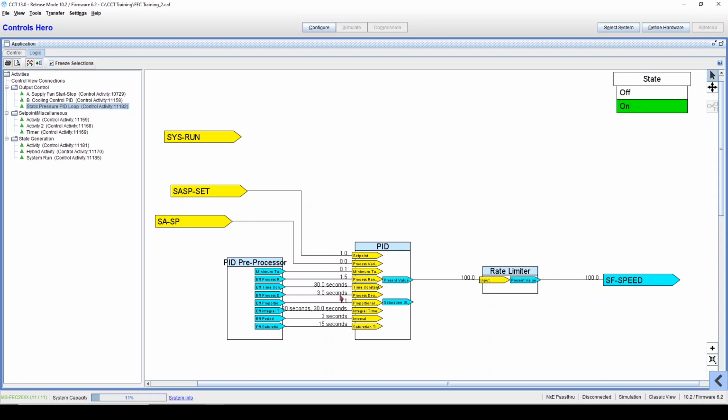Now let's increase my static. Right now we have zero, so I'm gonna go ahead and put, let's say, 1.1, just a bit above the 1 inch set point. Send the command and watch what's gonna happen. So my PID is gonna drop a little bit, not all the way down to zero. It's not a sudden change, but see how the rate limiter is kind of catching up with the PID.